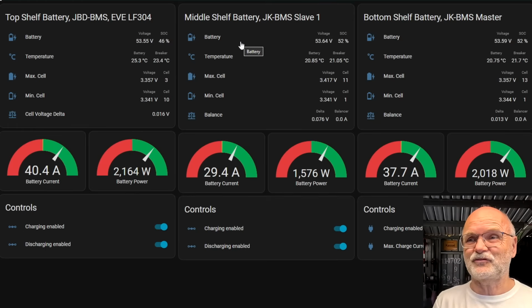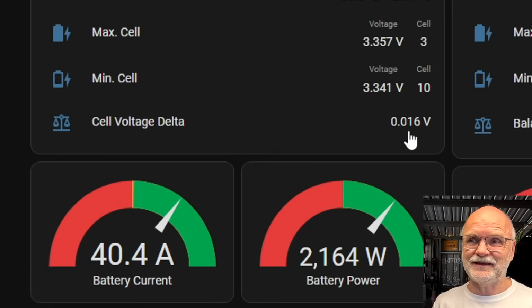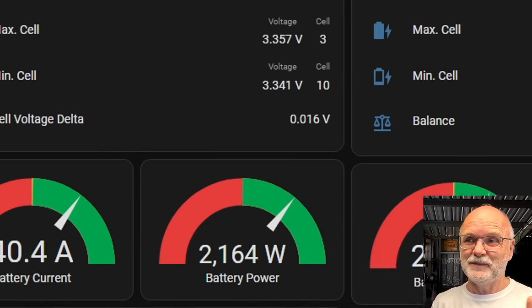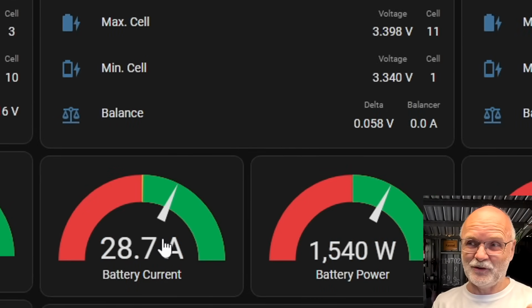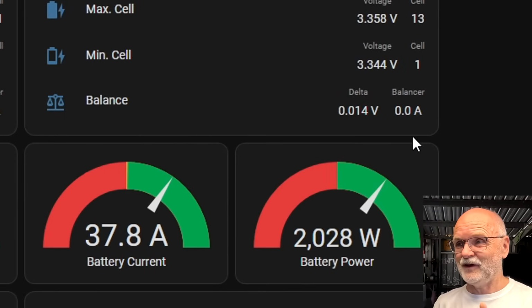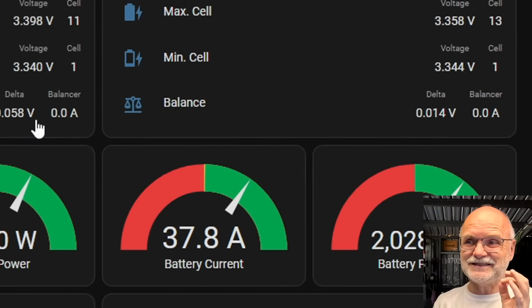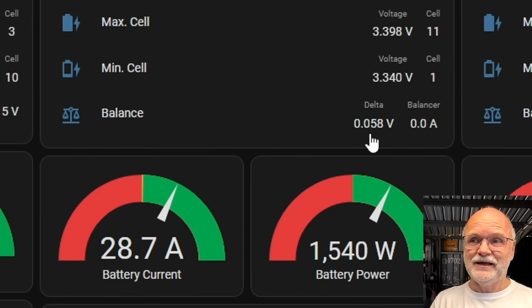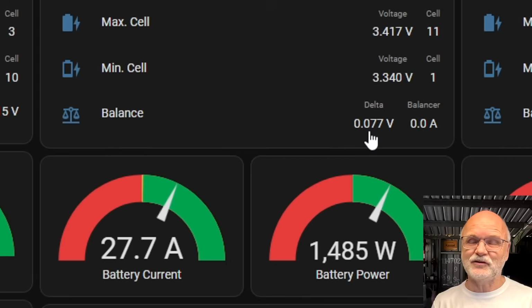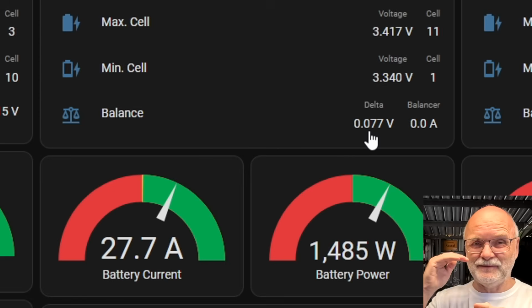You can see this on the screen already: top shelf has 16 millivolt deviation at the moment at 40 amps into the battery. The middle shelf, only 29 amps, has 60 millivolt deviation. Bottom shelf, 37 amps into the battery, 14 millivolt. You can see how high the deviation already is here, and when we push harder into the battery, we'll see this increase up to 150 millivolts. So there's obviously once again a problem with the aluminium terminals and the bus bars.